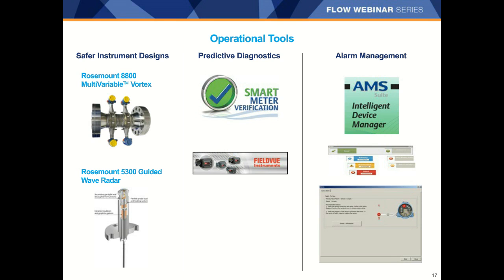A loss of measurement in the middle of a batch can not only create safety concerns, but it can also impact the ability to adequately complete the processing on specification. But Flow isn't the only business with such diagnostics. Fisher has great diagnostics through their FieldVue digital valve controllers, or DVCs. And once the FieldVue device has been correctly commissioned with all of the required data, it allows you to see all aspects of the valve's dynamic performance and mechanical integrity.